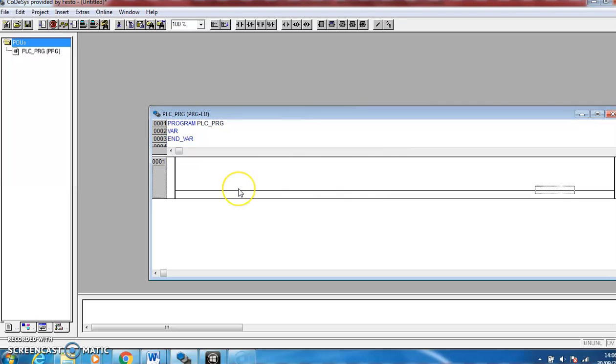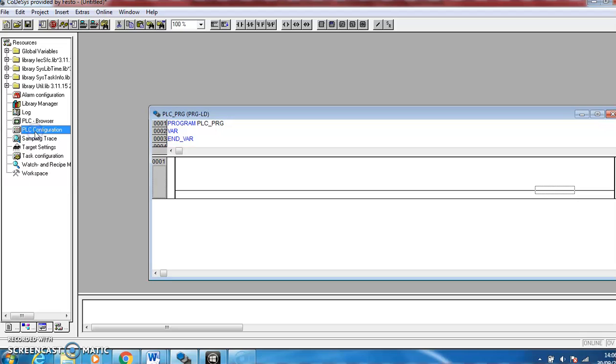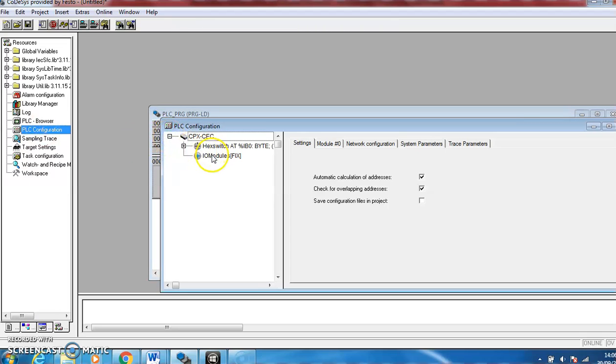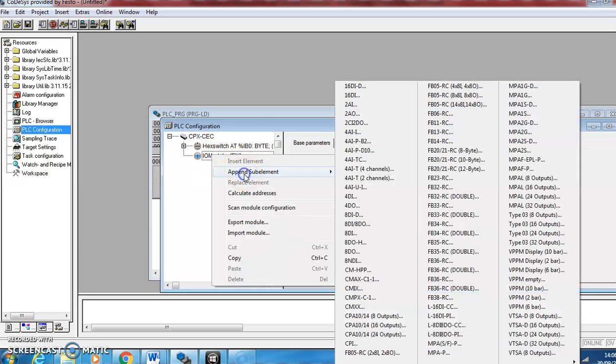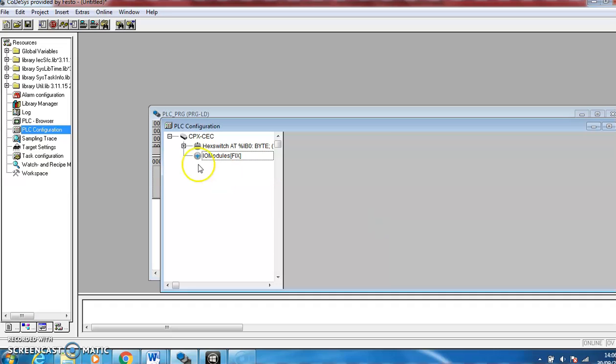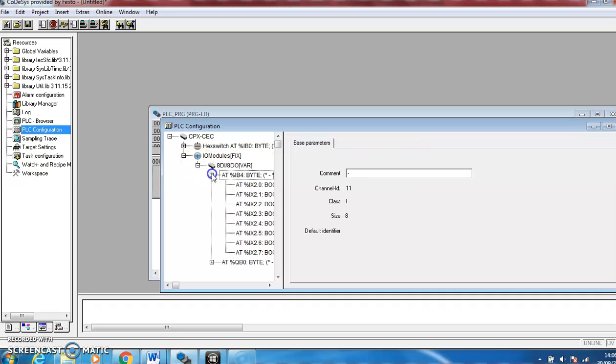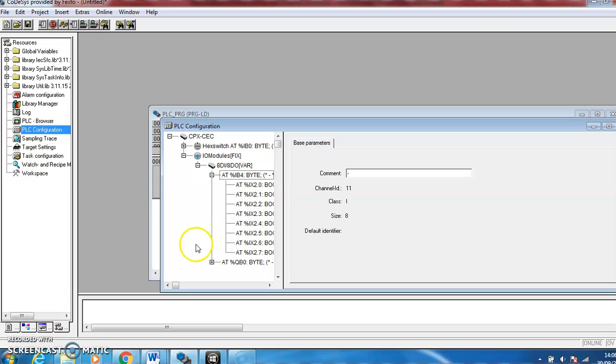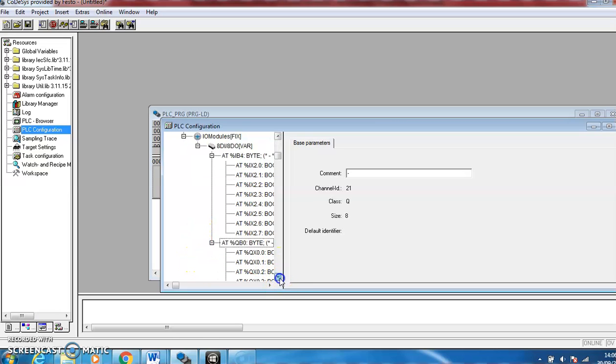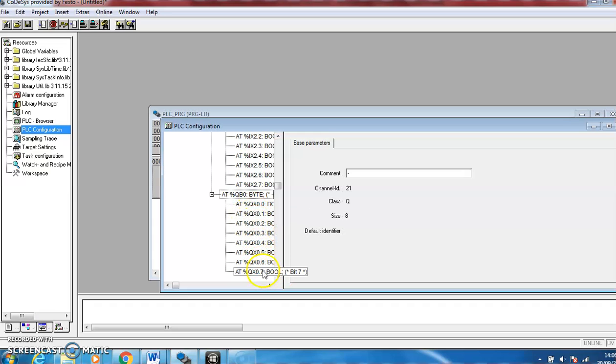We've got our little ladder here. So if you go to the fourth tab along, we need to configure the PLC. Add our IO module, so here right click, append subelement, and go eight digital in, eight digital out. Once we expand this we find that we have our inputs from IX 2.0 to 2.7 and our outputs addressed QX 0.0 to 0.7.